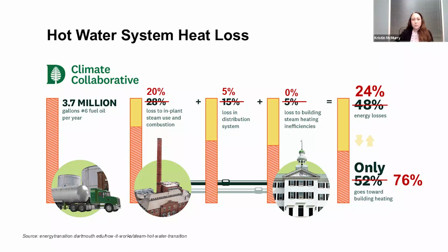Yep. So you still lose that 20% because in this example we're going to keep similar boilers, but now it's a hot water boiler still using natural gas. So we still lose 20% for combustion, but that 8% went away. You're now distributing at a lower temperature, so you have less heat loss, we're going to say 5%. The inefficiencies in the buildings are gone, and now your energy losses have been cut in half, so you're at 24% losses, and your COP has gone all the way up to 0.76. That's a pretty big improvement, and that's without doing any major changes within the plant, we could do heat pumps or heat recovery chillers. There's all kinds of different things you could do that would make that even better.